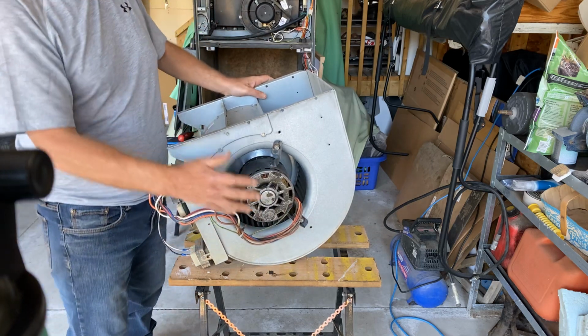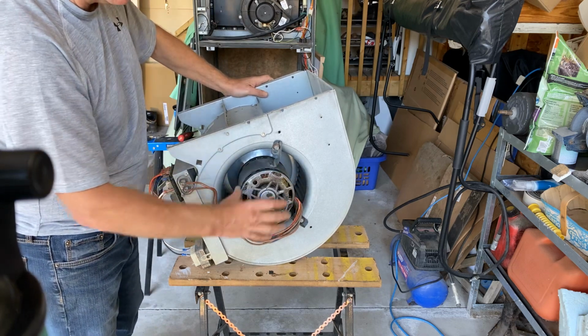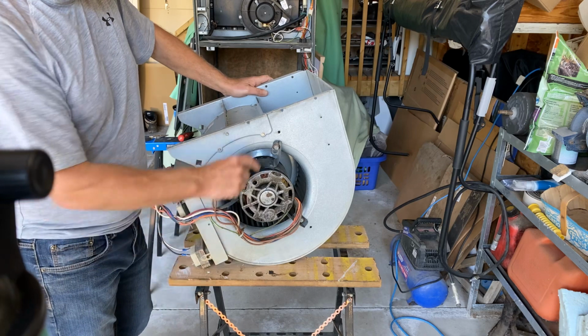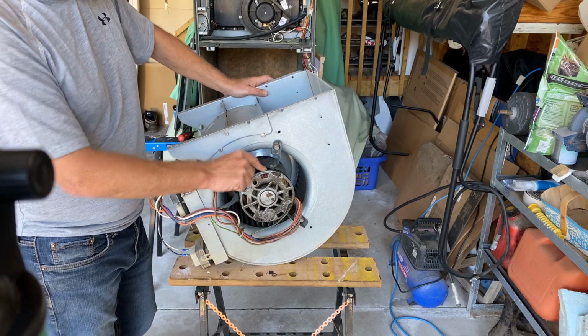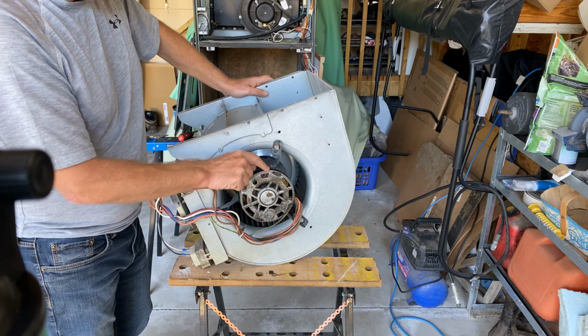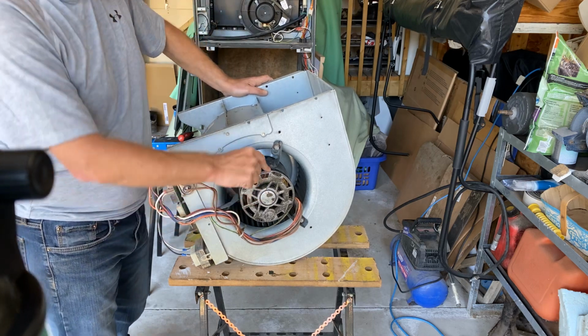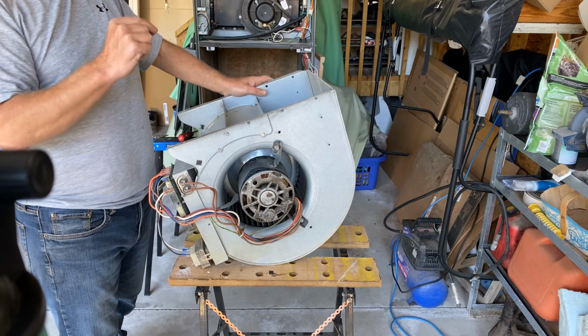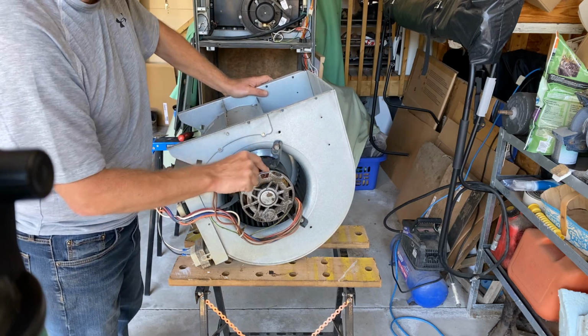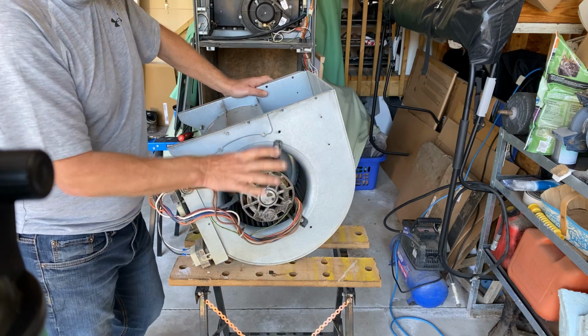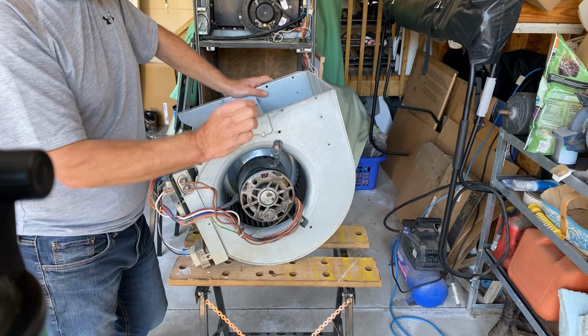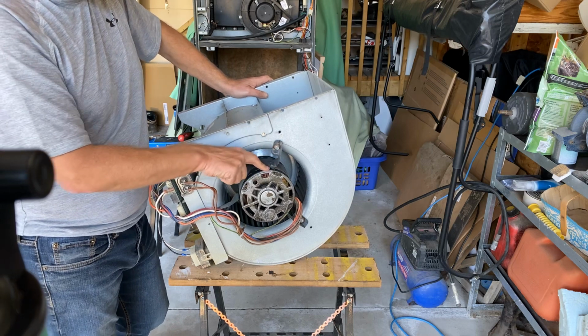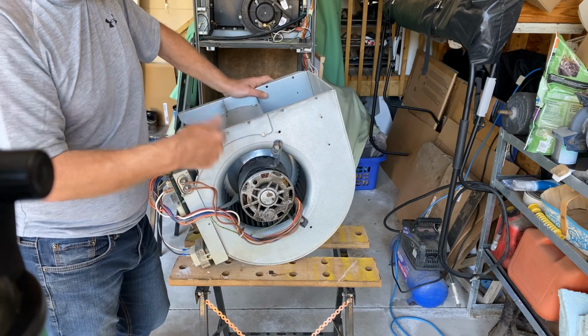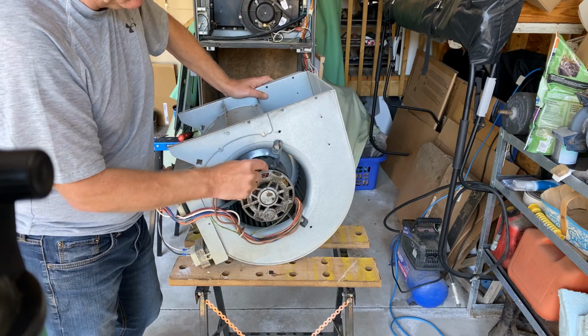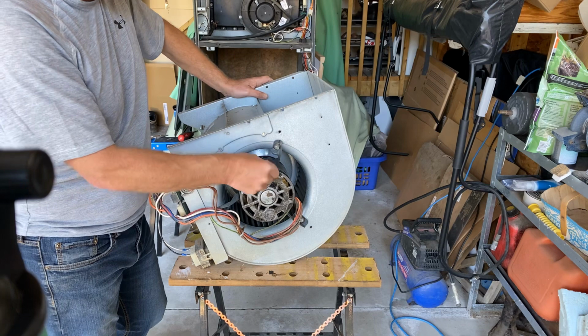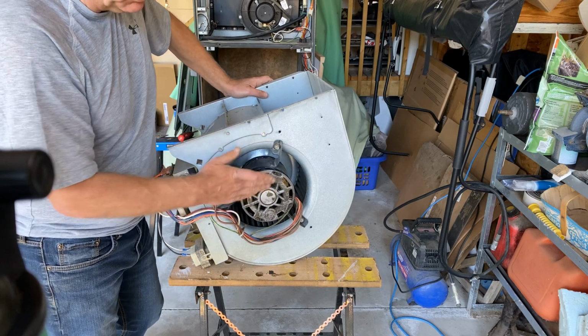The other thing to look at while this is out is whether there are any points of lubrication on this motor. If it was a lubricating style motor, there would be little pins, one here and one at the other end in the end bells, generally yellow plastic or silver aluminum filling a hole. If it could be lubricated, you'd pull those plugs out and put a few drops of motor oil, not engine oil, in those holes, then put the cover back on.